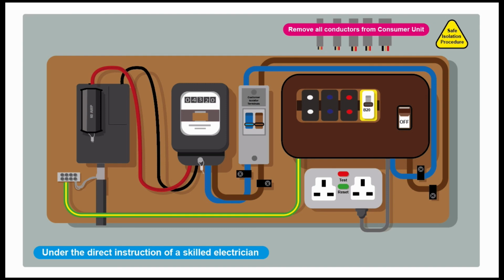Right, so that's the end of day one, and what have we achieved? Well, we've confirmed that we've got a good Ze, so we've got earth into the property. We're also happy with the supply cutout. We don't need to call a DNO to come and have a look at that. We've contacted the supply company, and they're going to send somebody around to fit an isolator so we can swap this fuse board out. We're going to stick with this fuse board for now because there's lots of dirty work which is going to get done, and we've got no conductors in yet, so we'll stick with this fuse board for now.